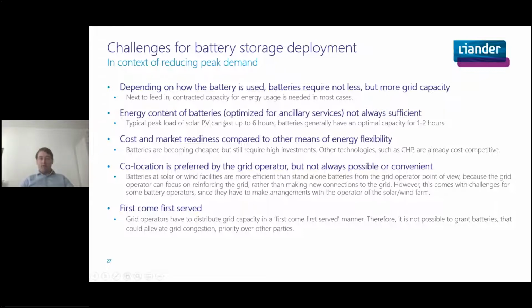Then there's the energy content of batteries. It's now optimized for ancillary services and therefore not always sufficient to solve congestion. A typical solar farm may have up to six hours of peak power, too much to feed into the grid, while batteries generally have a capacity optimal for only one to two hours. So there's still a mismatch between the capacity in the battery and the capacity that's needed.